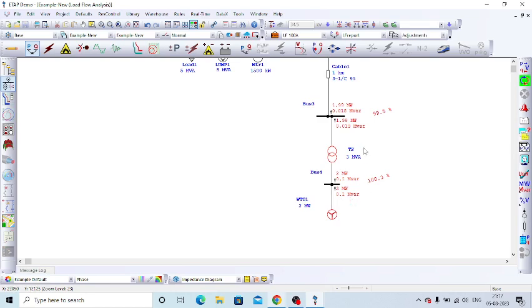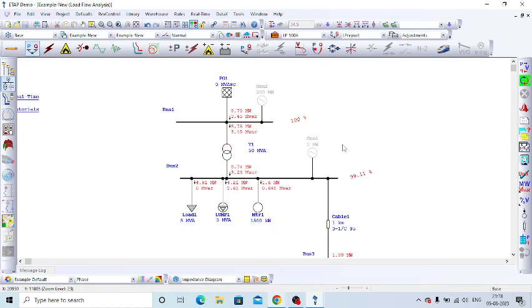You can see on this transformer high voltage side, it is not 0.1, it is 0.018, and the sign is positive. Last time it was negative, now it is positive. It means both real power and reactive power are flowing from this generator towards the system. Earlier, reactive power was consumed from the system by this transformer. Now the transformer is consuming the reactive power from the generator, so only the remaining reactive power is flowing into the system.